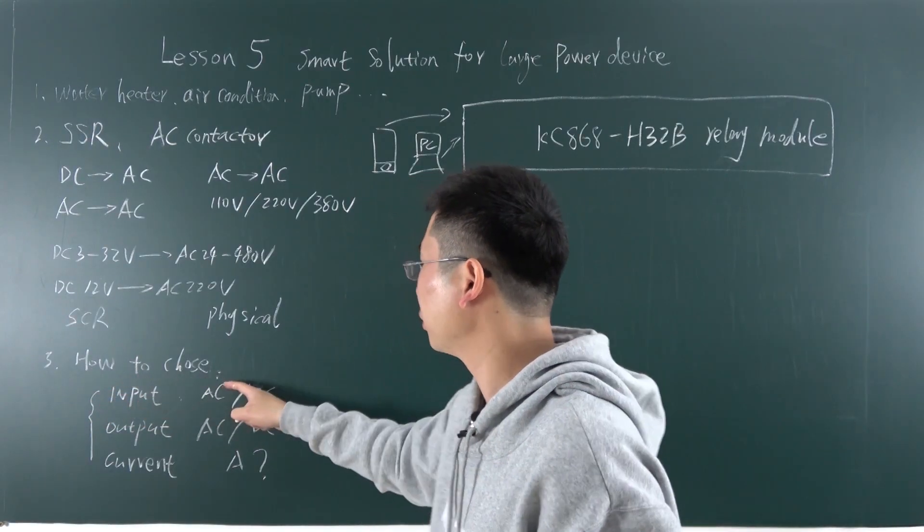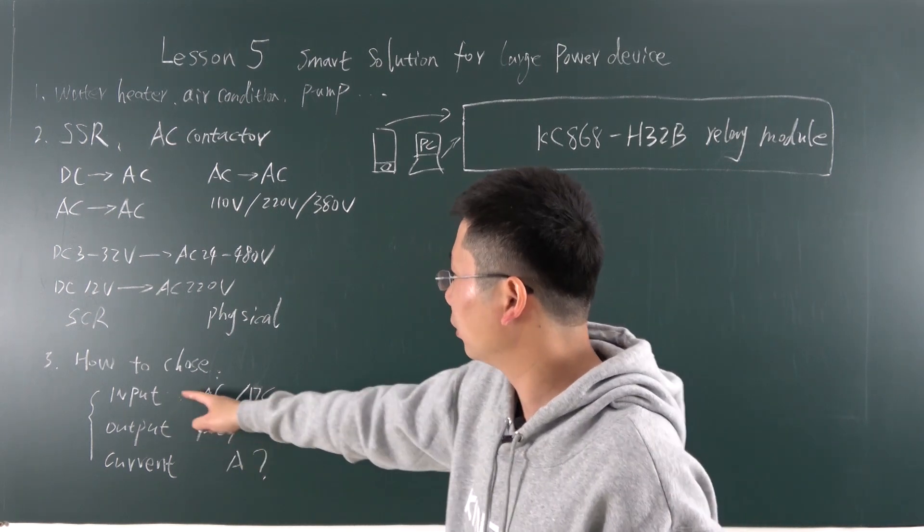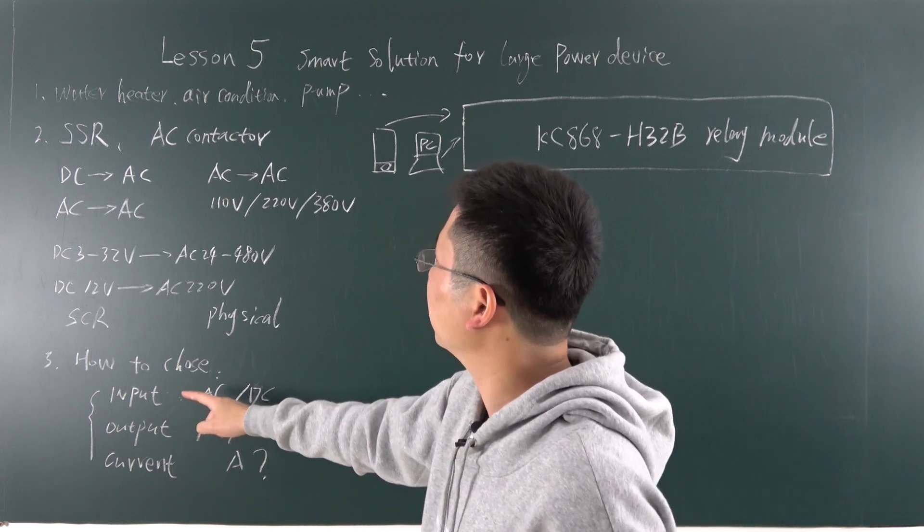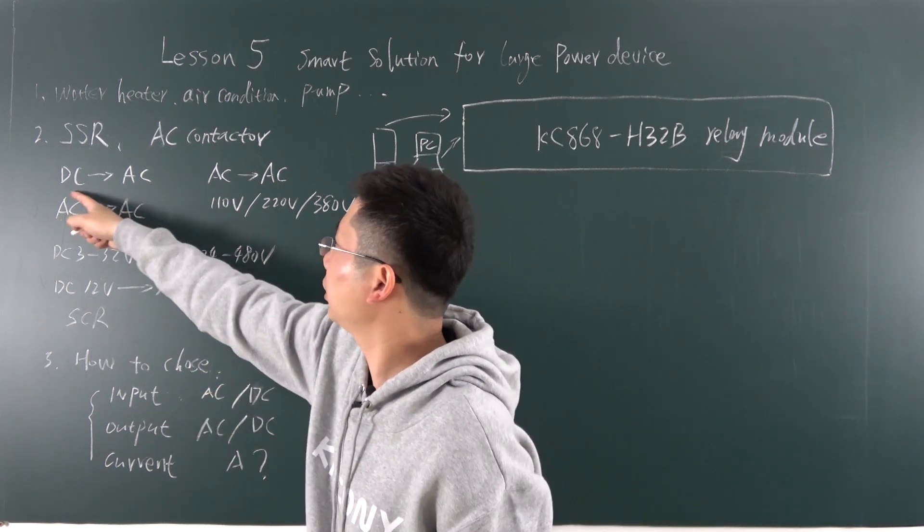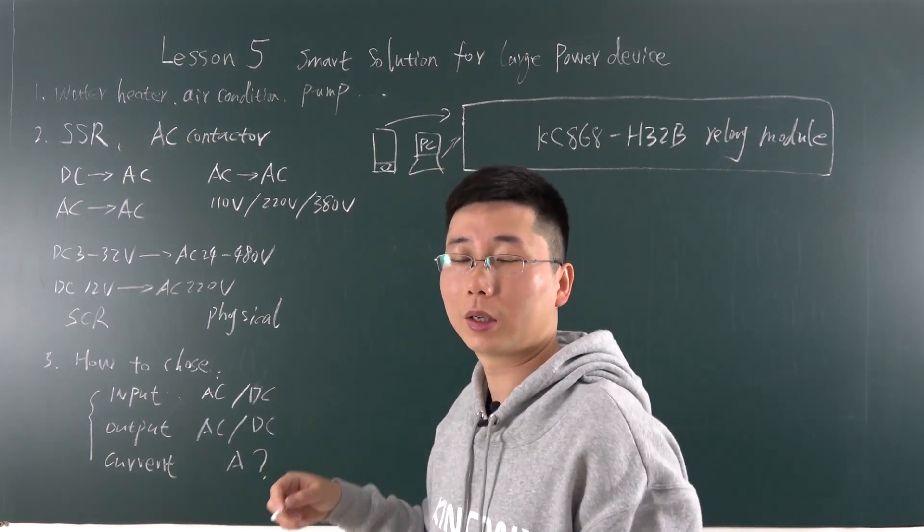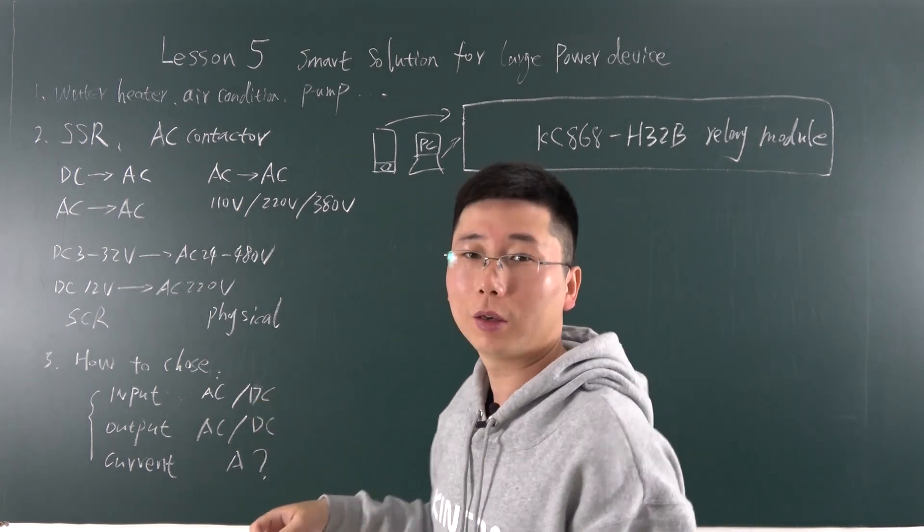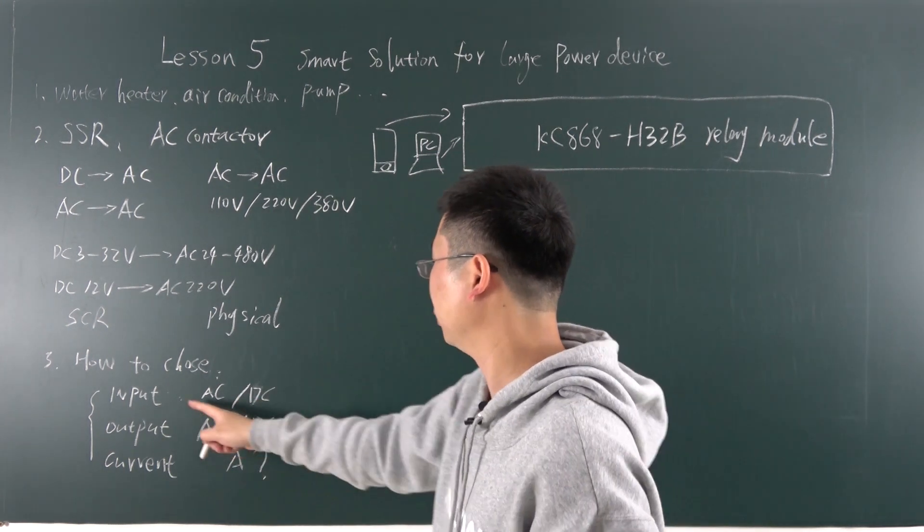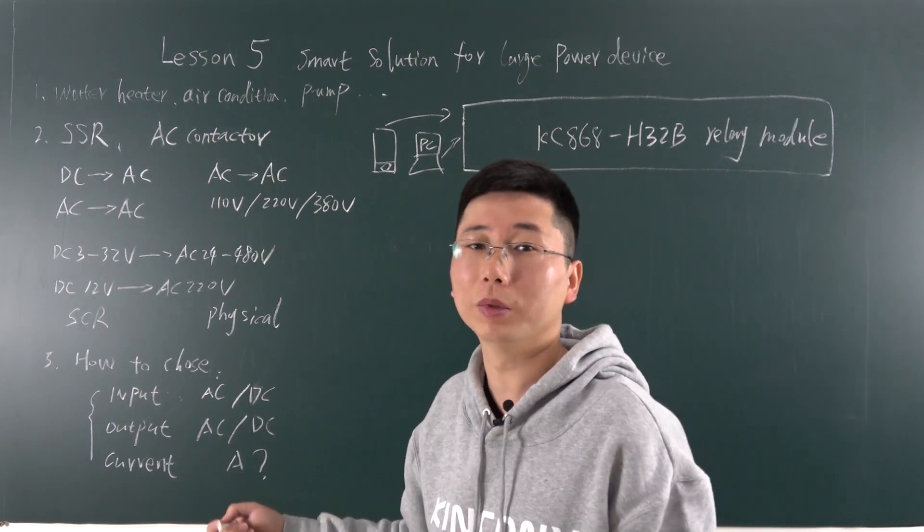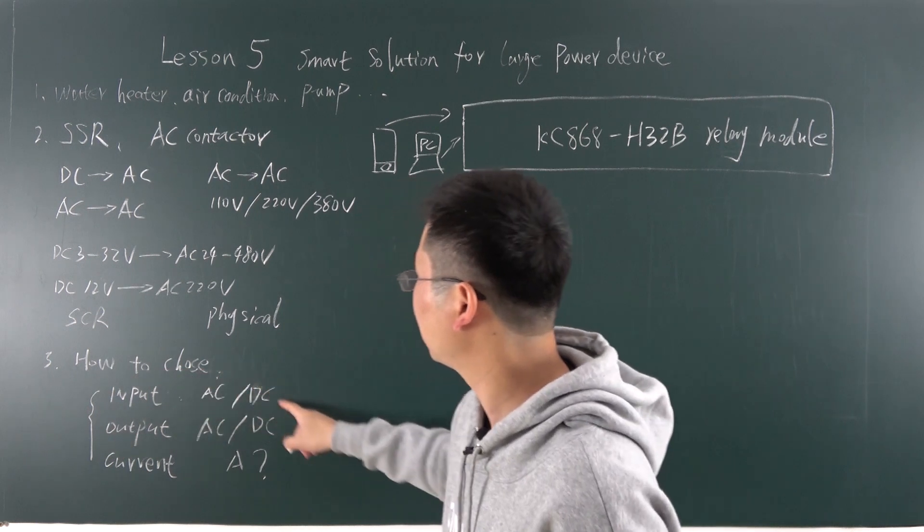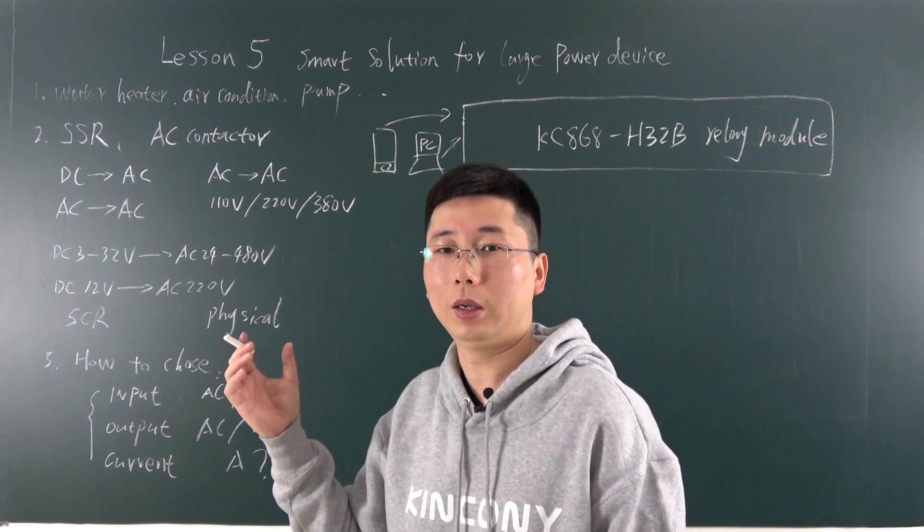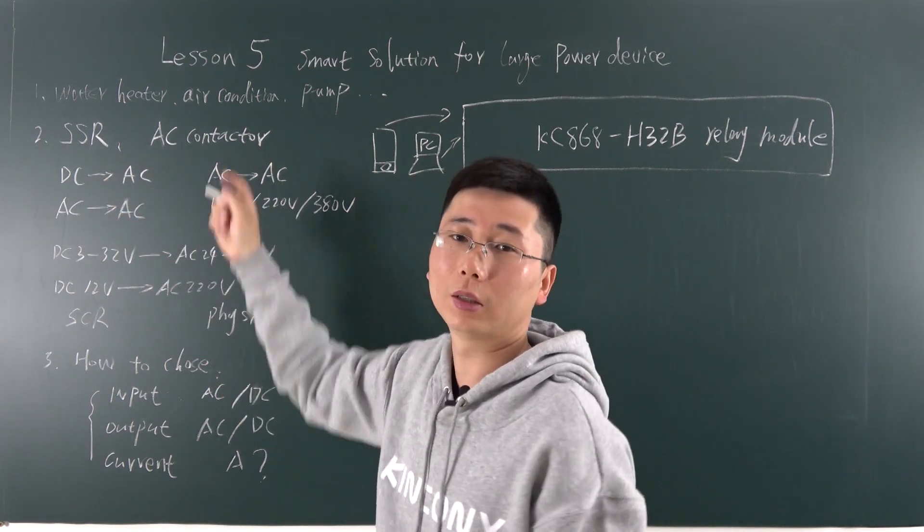Three, how to choose? We just need to confirm this input, output and the current. What input you will use. Like use DC or use AC. And what is output to control? Like you can control AC load. Or you can control DC load. It's up to you. And this is current. How many amperes your load will be used? Just these three settings. You can choose a SSR or AC contactor to use.